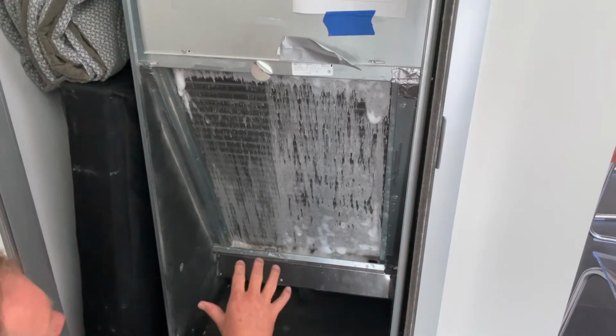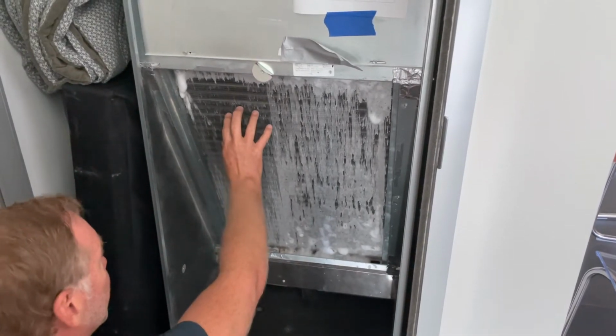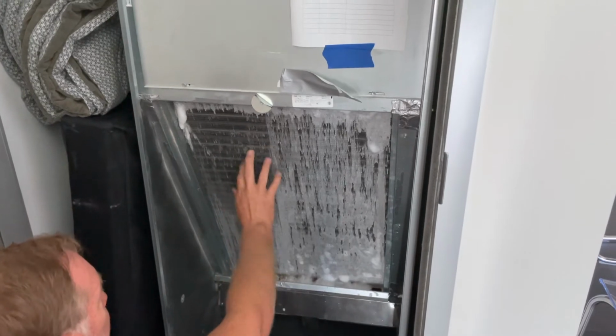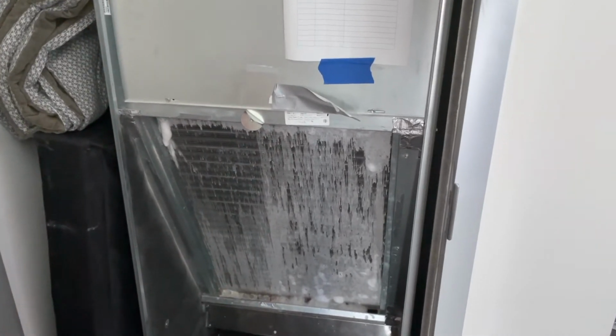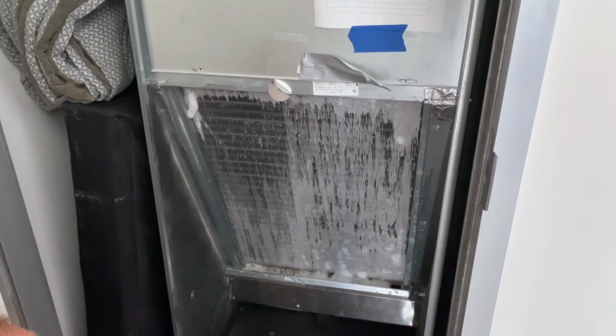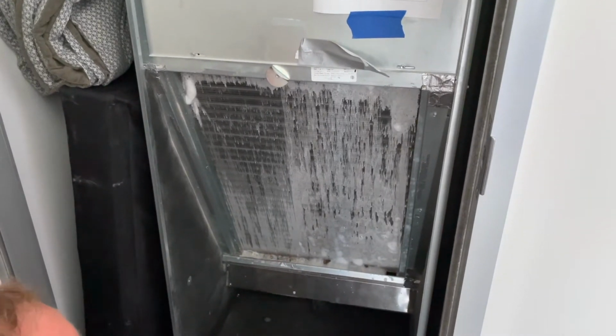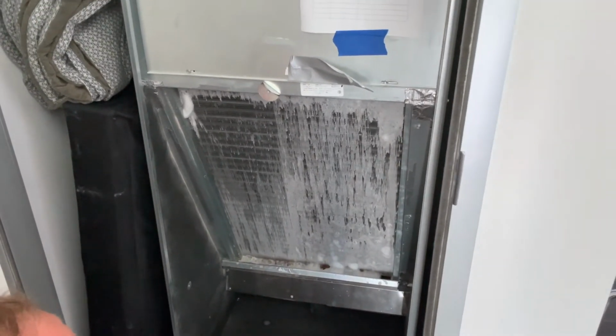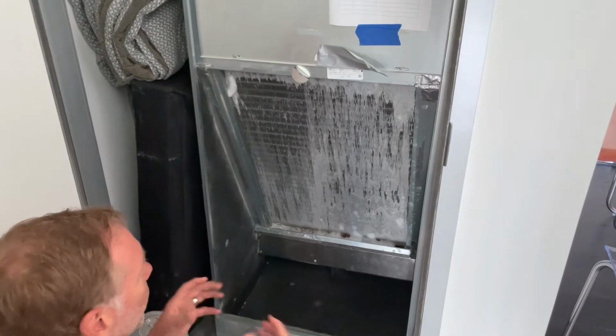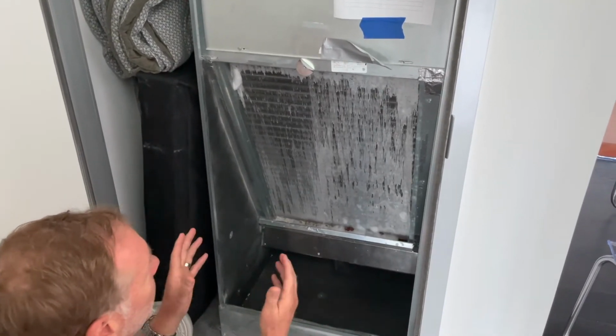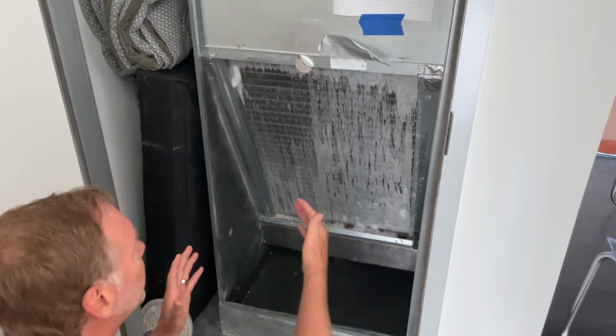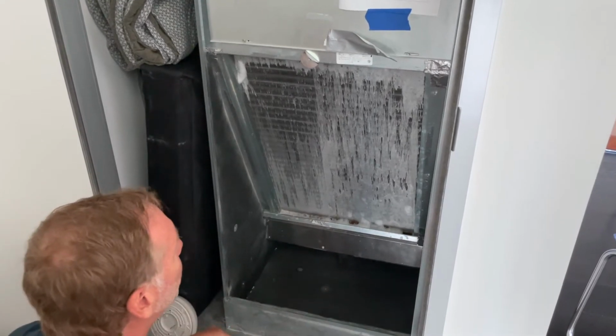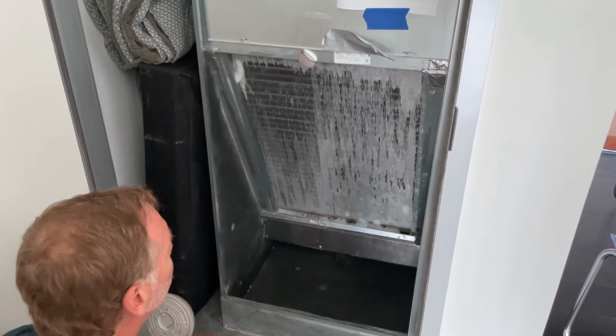The importance of this is keeping the grills nice and clean so you get a lot of airflow. This cleans out the grime and oils in the air—you don't want dust sticking to that and creating more sticky grime that plugs things up, since you want easy airflow for maximum cooling from the fan.